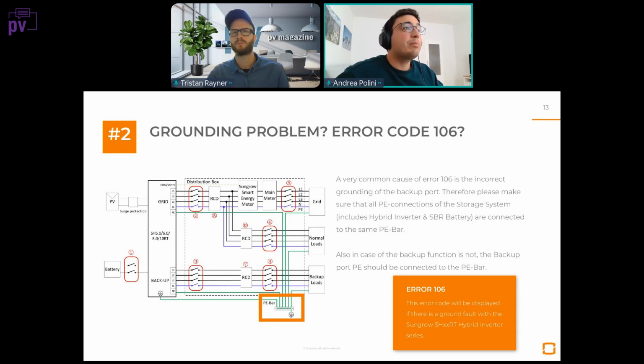So there's the PE of the backup, the PE of the grid, and also the PE of the backup loads and of the normal loads should come directly to one potential point. So we have basically one point where all the grounding cables are coming, and this helps a lot with the communication signals, especially communication between the meter and inverter, battery and inverter, and also for the stability of the backup function. So the backup function will work at best when there is a constant potential of grounding between the normal grid and normal loads and backup loads, and also compared to the grounding of the inverter.